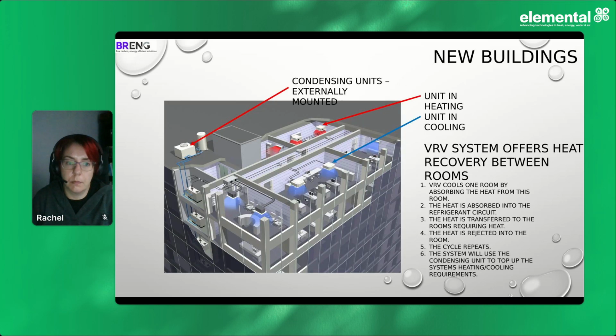What that does is it improves its efficiency because you link a system together. So some rooms might need heating, some rooms might be really warm and need a bit of cooling. When we talk about cooling, what we'd say is you don't set your cooling system to cool to 23 degrees. Set it to stop it from overheating. So set your high limit of your room to about 26 degrees. Now in the summer, 26 degrees doesn't feel that warm compared to an outside temperature of 30 to 35 degrees. If you have a temperature in the school lower than 26 degrees in the summer, what you'll find is when you're going out, you'll feel really, really hot. When you come in, you will actually feel really, really cold because of the temperature difference.